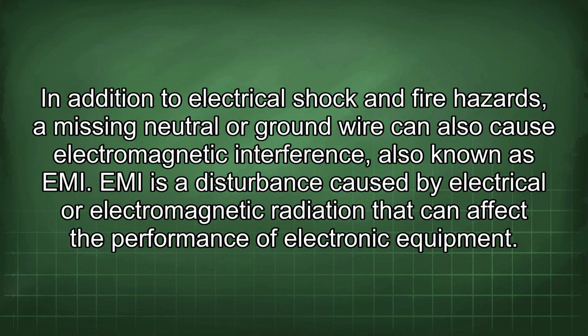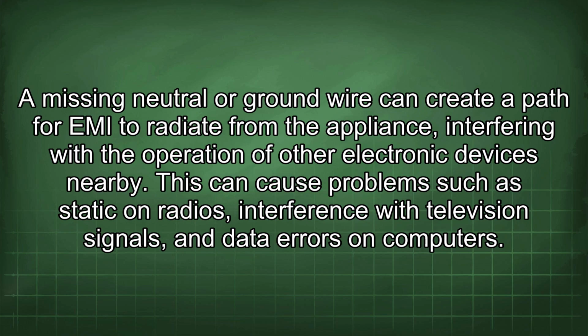In addition to electrical shock and fire hazards, a missing neutral or ground wire can also cause electromagnetic interference, also known as EMI. EMI is a disturbance caused by electrical or electromagnetic radiation that can affect the performance of electronic equipment. A missing neutral or ground wire can create a path for EMI to radiate from the appliance, interfering with the operation of other electronic devices nearby. This can cause problems such as static on radios, interference with television signals, and data errors on computers.